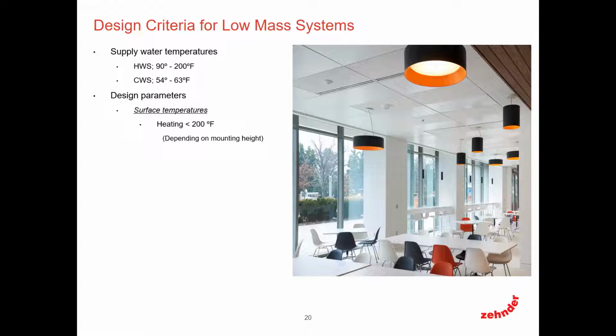On the heating side, generally, you don't want to go above 200 degrees on your surface temperatures. Now, the first question I get all the time is, Mike, do you want to put 180 degree water through an 8 or 10 foot mounted panel? Absolutely not, because the intensity is going to be so high that you're actually going to create a level of discomfort for the occupant. So ASHRAE and the committees have determined and come up with standards that basically say, depending on the mounting height of the panel, and depending on how much active surface area is within the ceiling space itself, will drive what your average surface temperature should be, so you don't create a level of discomfort for occupants.